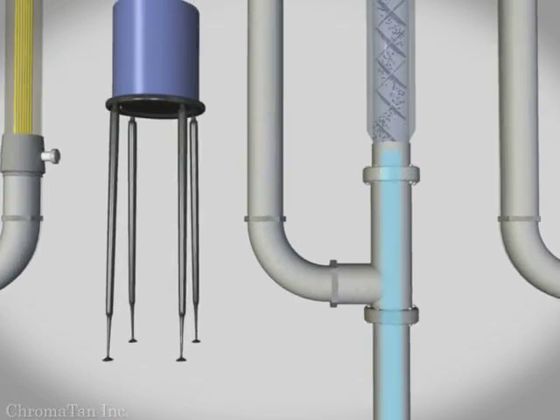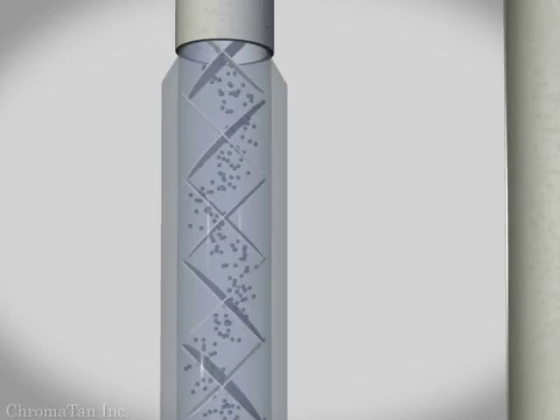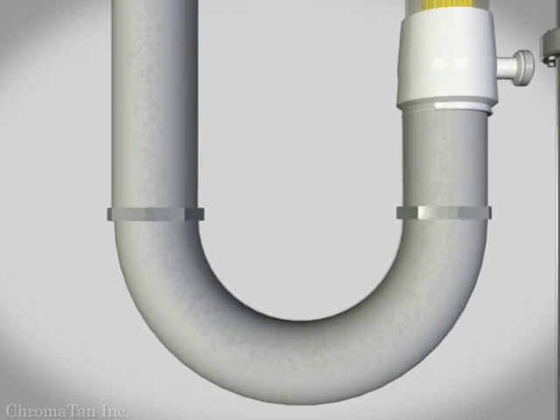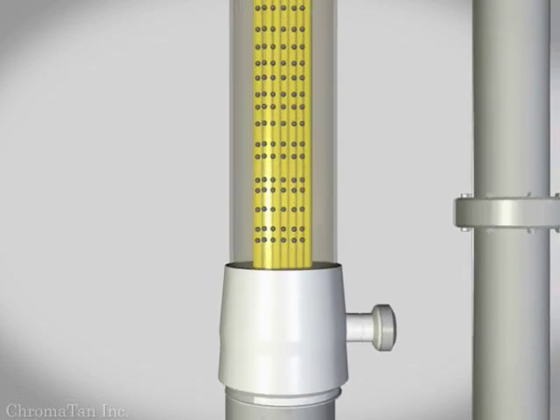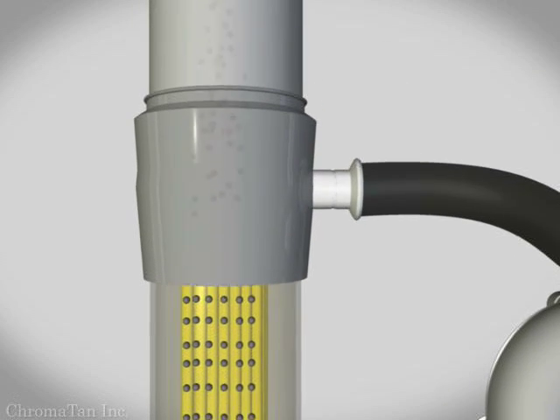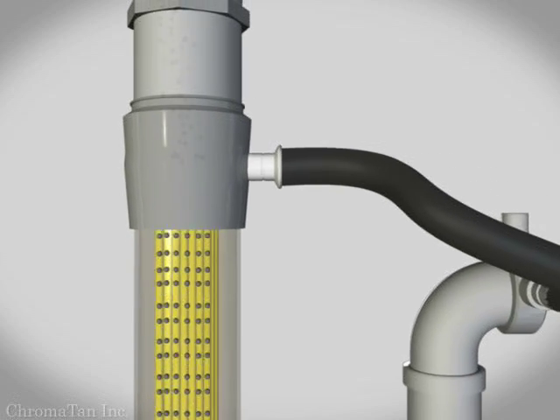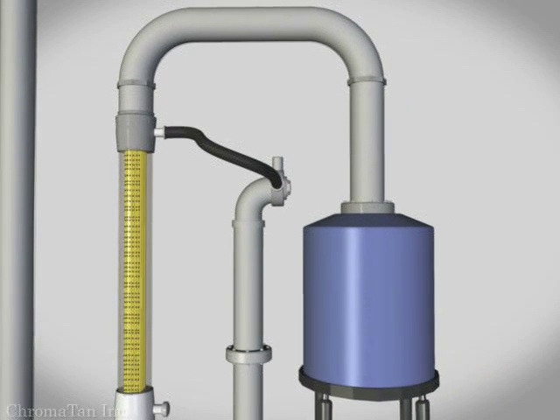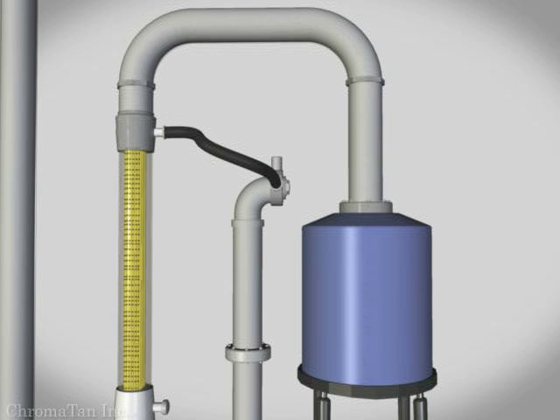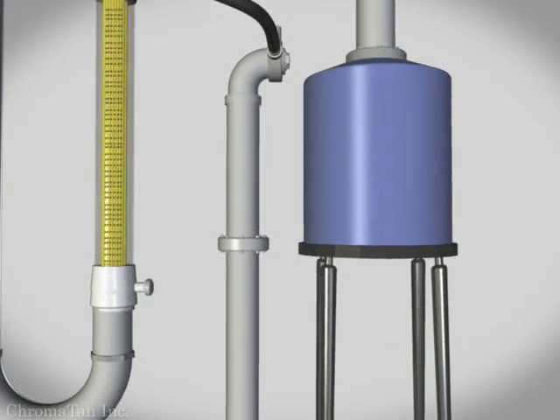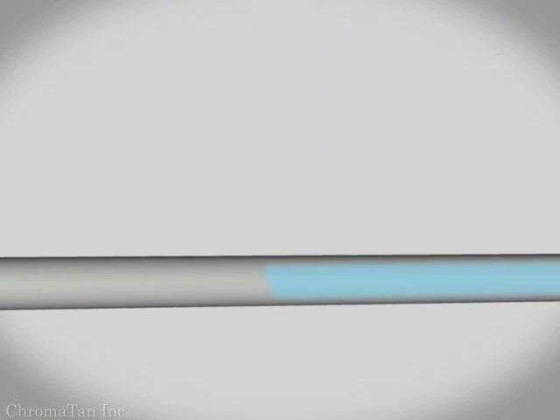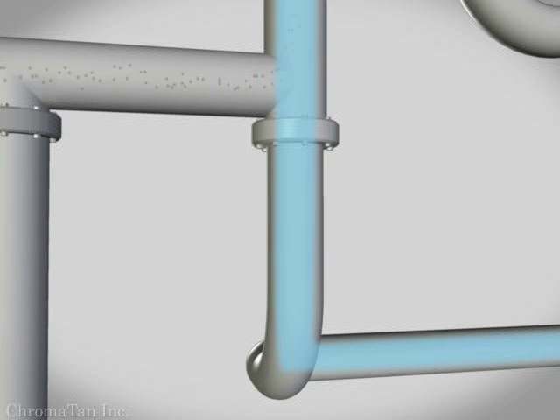The second stage of the CTC system is designed to boost recovery to 95 percent. In the second static mixer, the slurry is once again diluted with elution buffer. The dilute slurry is then passed to the second hollow fiber module, where it is re-concentrated, recovering antibodies left over from stage 1 in the permeate stream. While the slurry cycle finishes in the second slurry tank, the permeate stream from the second hollow fiber module that contains the recovered antibodies is recycled via a recycle line back to the static mixer that is part of stage 1. This completes the counter-current recycling loop and the batch elution operation of the counter-current tangential chromatography system.